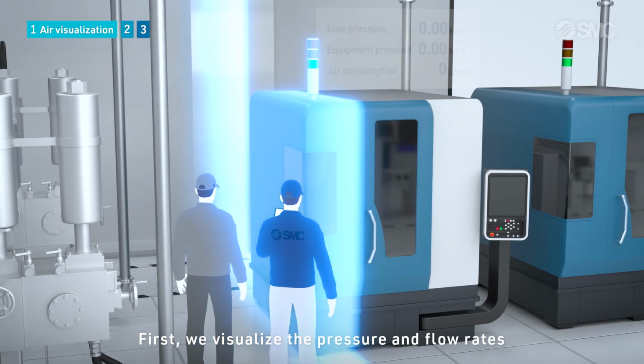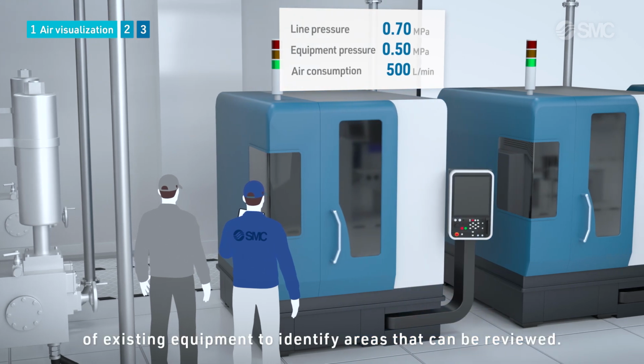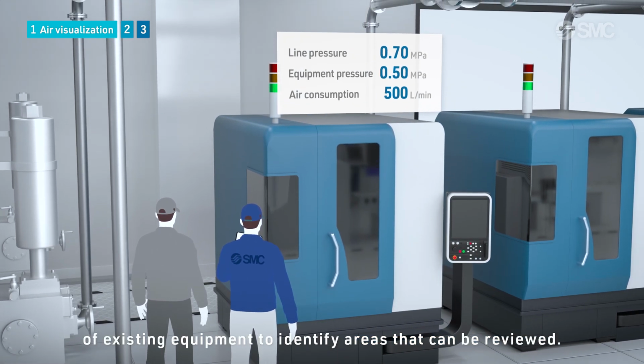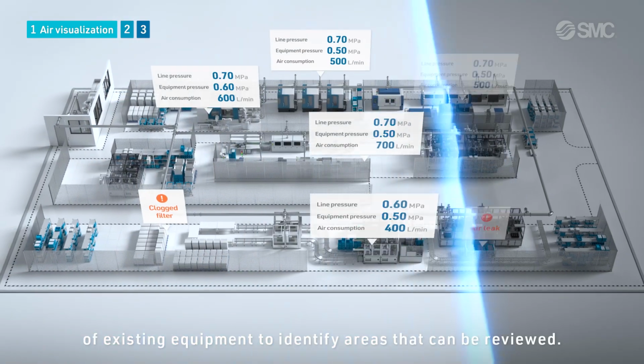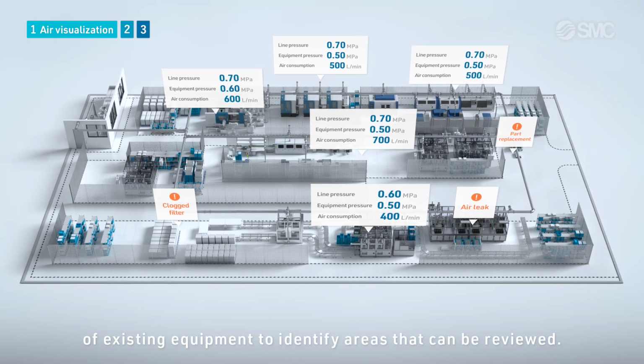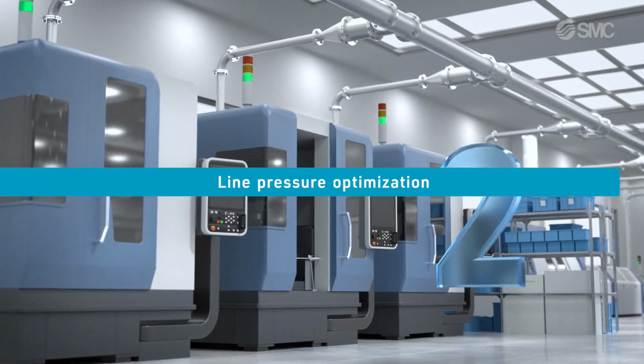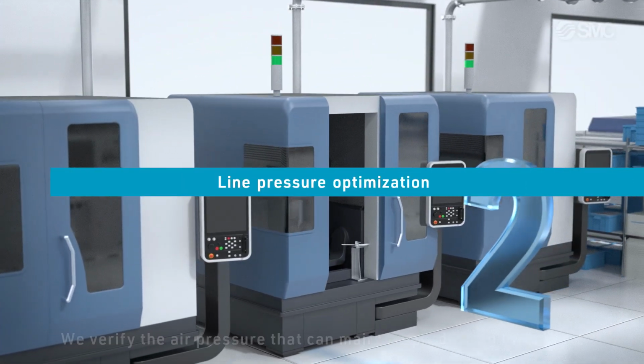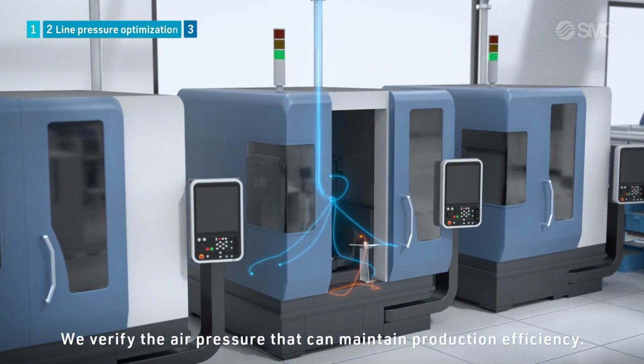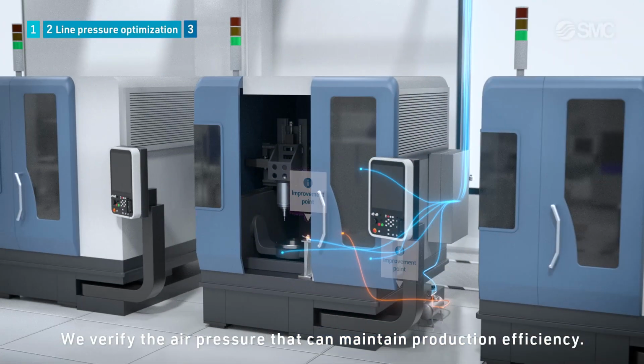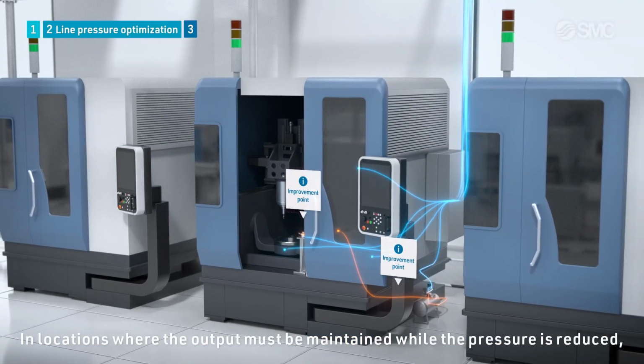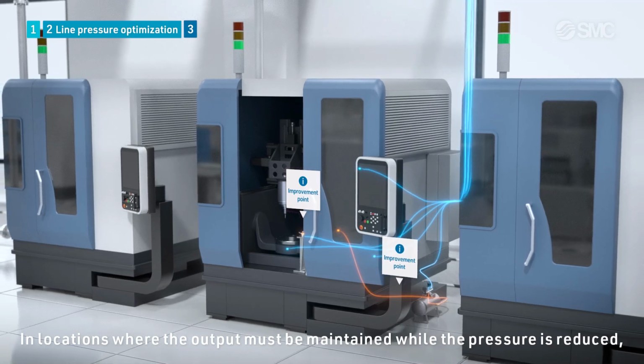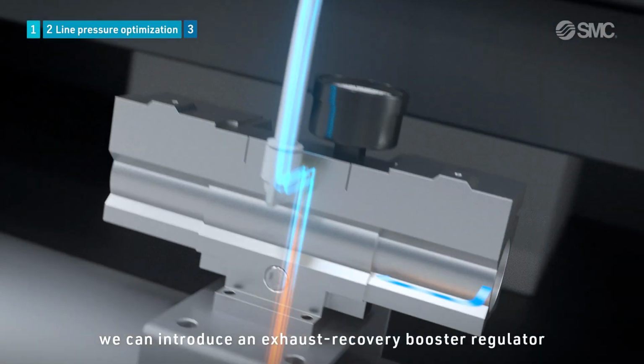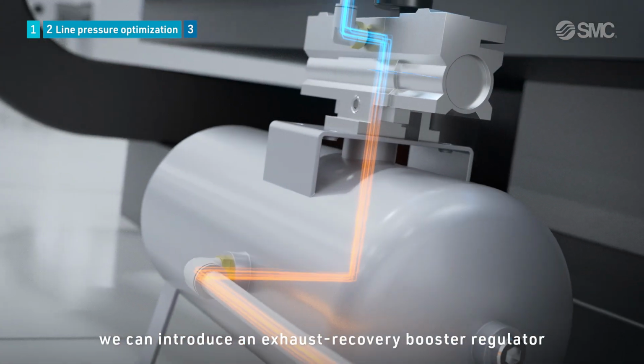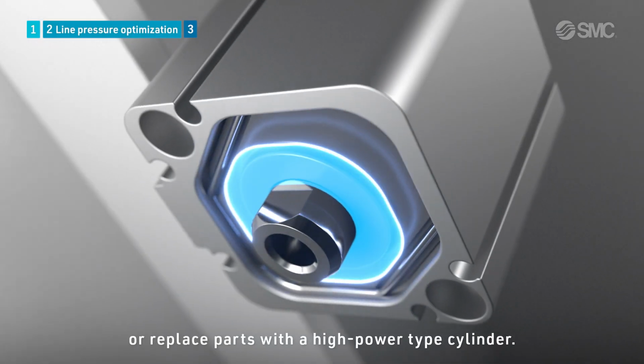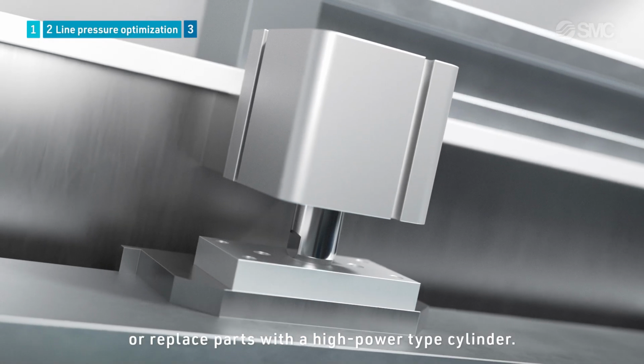First, we visualize the pressure and flow rates of existing equipment to identify areas that can be reviewed. Step 2. Line pressure optimization. We verify the air pressure that can maintain production efficiency. In locations where the output must be maintained while the pressure is reduced, we can introduce an exhaust recovery booster regulator or replace parts with a high-power type cylinder.